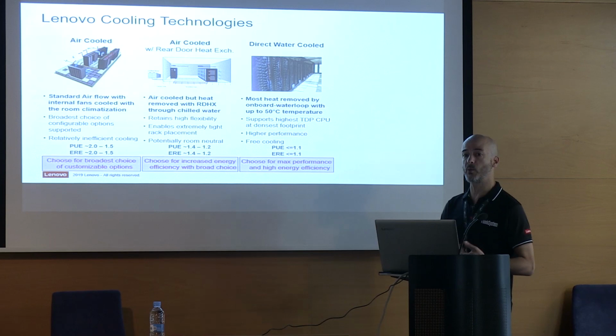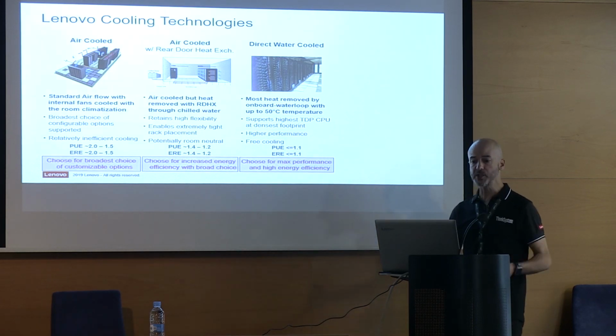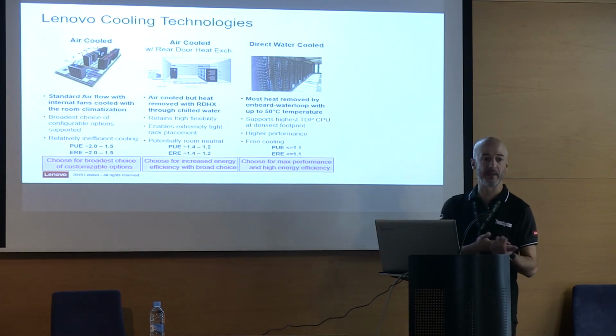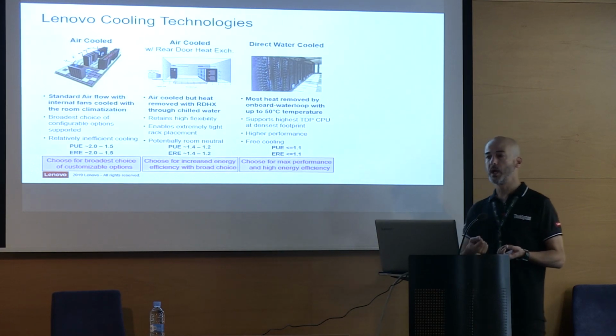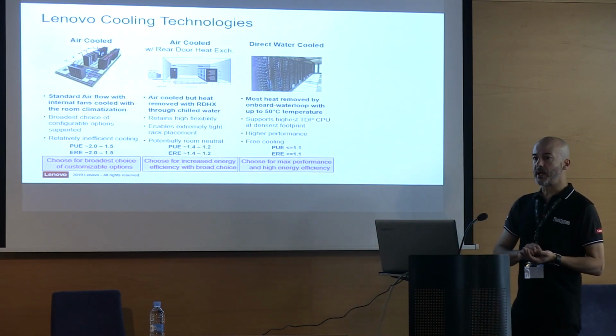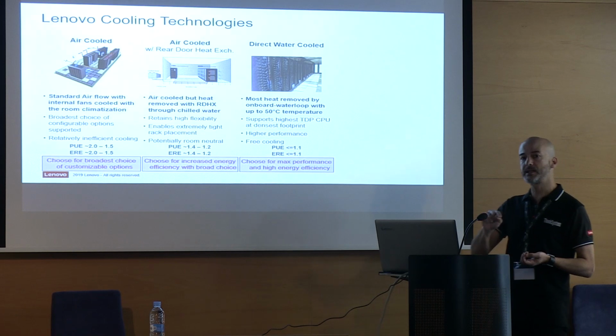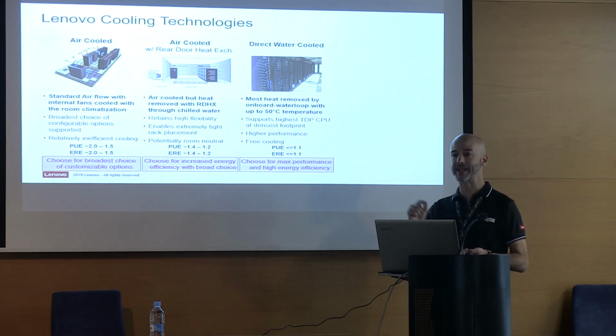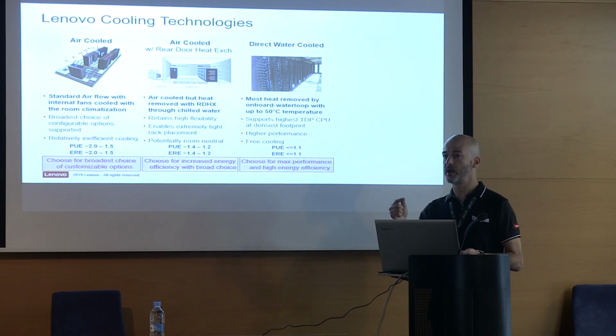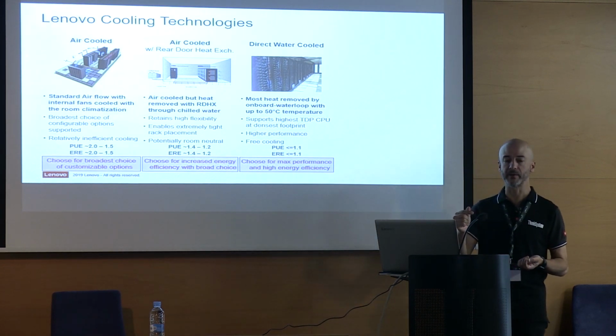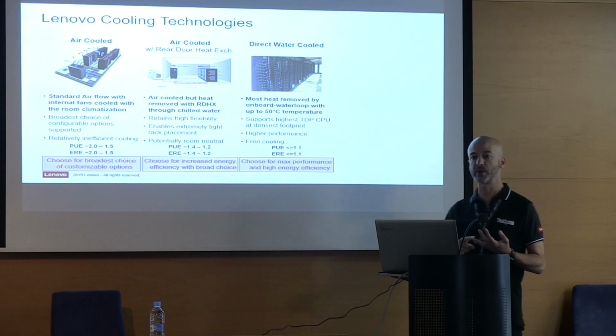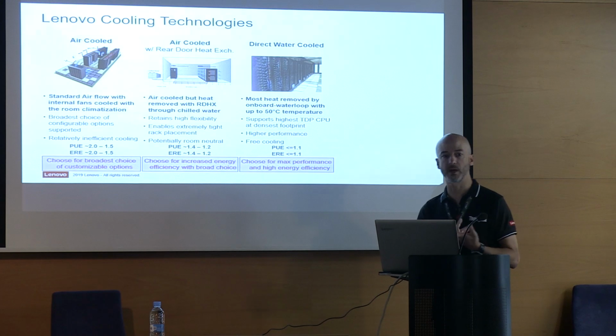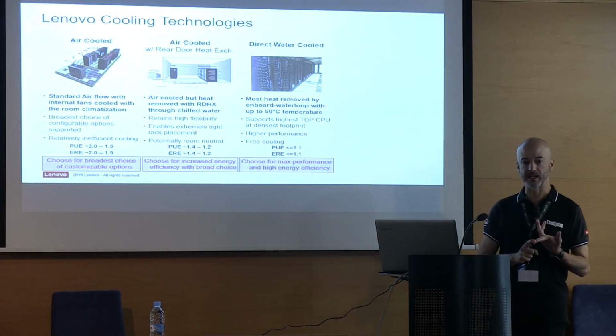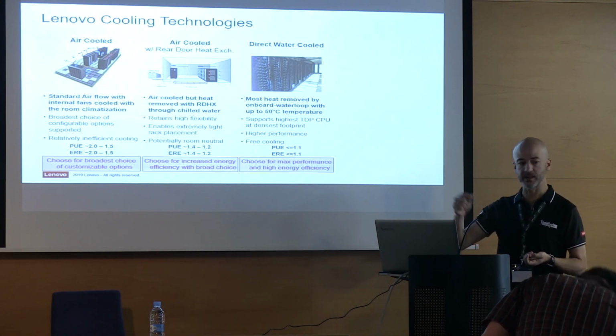That's why we're approaching this issue with direct water cooling. That means we make water circulate in a loop inside the compute node, cooling all the relevant components such as the processor, memory DIMMs, network cards, or hard drives. That's very efficient, and we can describe it a bit more in the next minute.